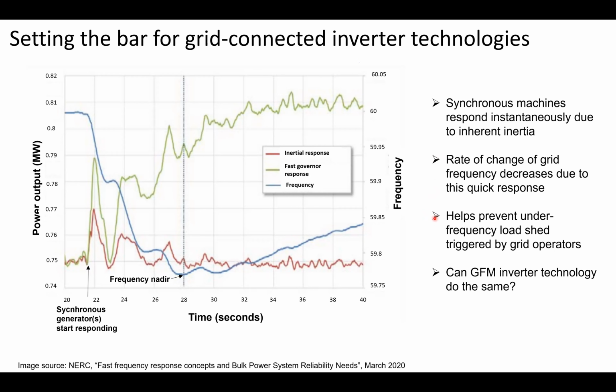So generally, as most of you know, most converters connected to the grid are grid following: they detect your frequency, act through a droop after a delay, and then respond. We expect grid forming, through simulations but also in practice, because it's controlling its voltage phasor, to have a more instantaneous response or inertial type response. So those are the characteristics that we wanted to see while connecting grid forming to KIUC's grid and see how it plays out. In the next few slides, we'll go through a few successes we've had. But yeah, just something that we want to achieve moving forward for all of our plants connected to these types of grids.